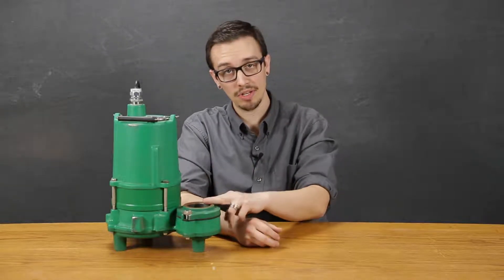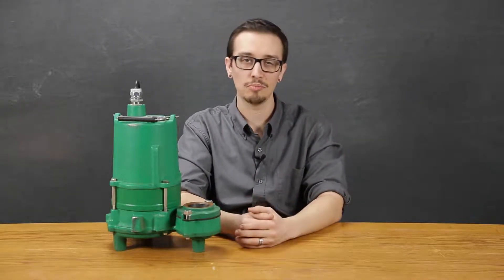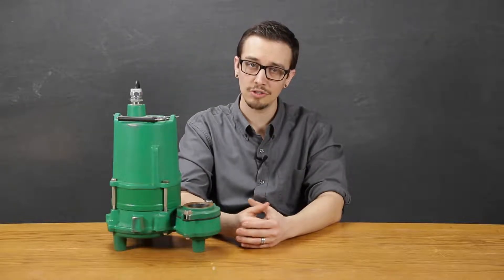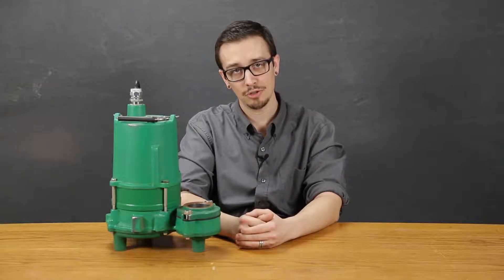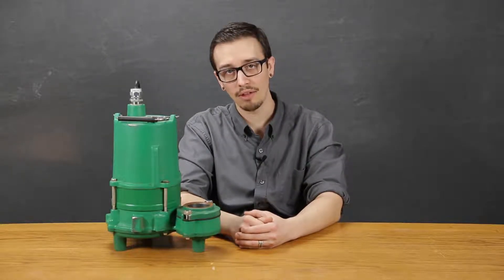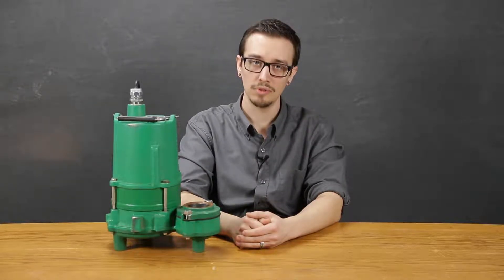A 2 inch NPT discharge is standard on this pump. However, a 3 inch discharge is orderable as an added option. The impeller is a two vane cast iron impeller and cast iron holds up very well to the caustic nature of the effluent.